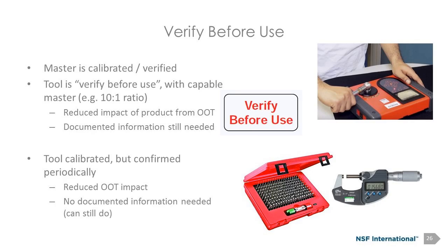The next one is regarding verify before use. And this is something we see all the time as auditors, and I'm sure you've seen it in your careers. Now, with a verify before use, what we're doing is we're calibrating or verifying this master, this torque control type unit, right? Or maybe the micrometer that's being used to verify these pin gauges. And then we're going to confirm the pin gauge each time, or we're going to confirm that torque is accurate because it's being adjusted or set each time. We're going to confirm that it's reading good. Perfectly fine. We want to make sure we're using the right master, or we're using the right gauge associated with that, using maybe a 10-to-1 ratio or whatever number you come up with as a company.